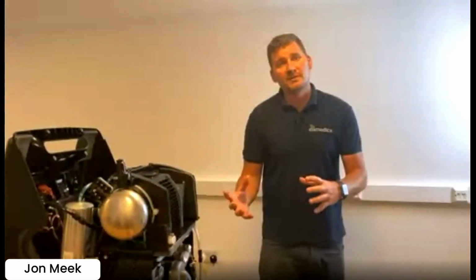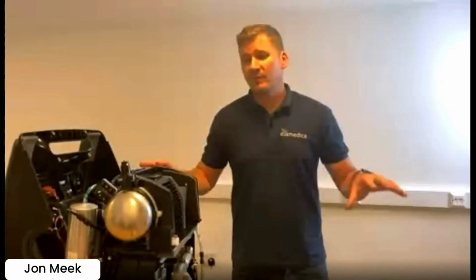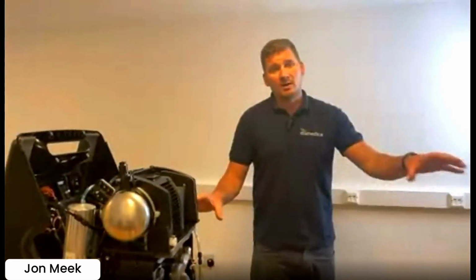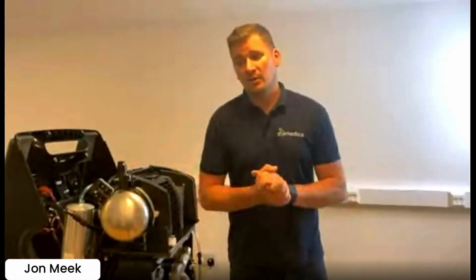And like I said before, the higher the flow rate means you can provide it to higher weights at a time. So our CPAP 10, which is 5 litres of oxygen, 5 litres of air, is only up to 5 kilograms. But if you want to use it on larger infants, up to 20 kilograms, that's when the higher flow rates are needed. So on the first one, we didn't have 2. So we just had the one model up to 16 litres. Now we've split it into 2. We have a lower weight and a higher weight one, which is CPAP 10 and 20.